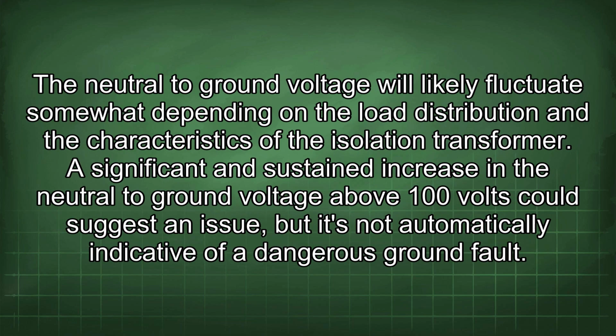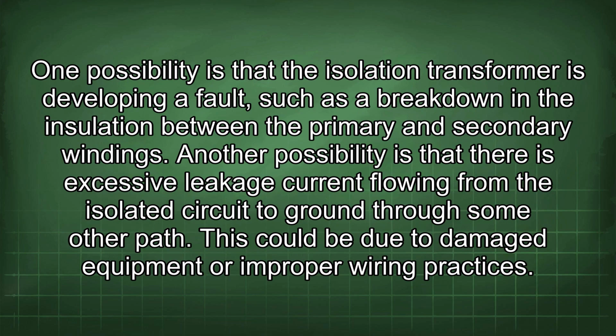The neutral to ground voltage will likely fluctuate somewhat depending on the load distribution and the characteristics of the isolation transformer. A significant and sustained increase in the neutral to ground voltage above 100 volts could suggest an issue, but it's not automatically indicative of a dangerous ground fault. One possibility is that the isolation transformer is developing a fault, such as a breakdown in the insulation between the primary and secondary windings. Another possibility is that there is excessive leakage current flowing from the isolated circuit to ground through some other path. This could be due to damaged equipment or improper wiring practices.